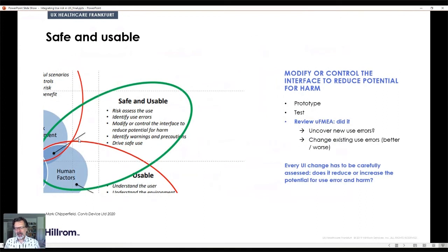So unfortunately, with medical devices, everybody knows that there's lots of documentation. This, for me, proved to be really, really worthwhile to start very, very early, and to do all the 600-700 lines of use error assessment really early, because then I can see if I change the interface at this point for this task, for this use error, what can I do actually?